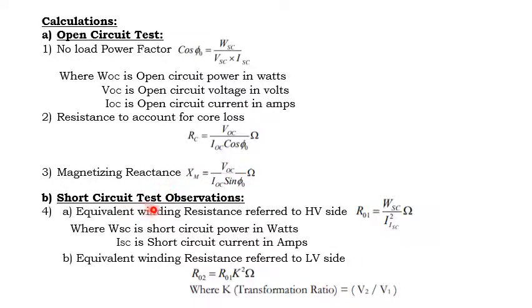Now, by the short circuit test observation, we need to calculate these parameters. The equivalent winding resistance as referred to the HV side. HV side means the primary side, that is R01. So that can be calculated as WSC divided by ISC square. This is nothing but the copper loss component, that is WSC is equal to ISC square into R01. So R01 is equal to WSC divided by ISC square, where WSC is the short circuit power in watts and ISC is the short circuit current in amperes.